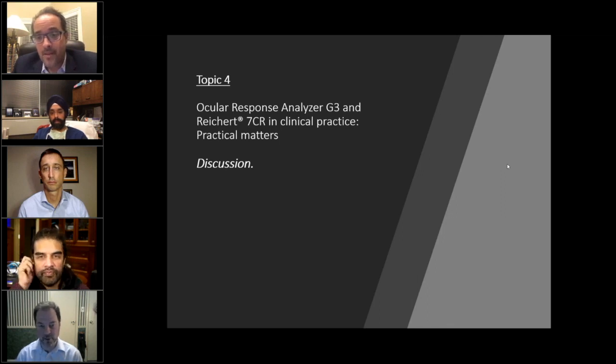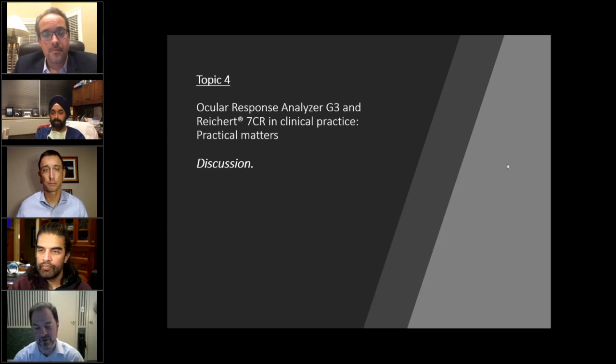That's right. Actually, that's when we really got a handle on what we were measuring: by looking at pre- and post-LASIK measurements and noticing how the two applanation events, what we call P1 and P2, changed in a different manner. The IOPCC algorithm was derived from pre- and post-LASIK data. We basically found a way to make the pressure stay the same in a pre- and post-LASIK population, and then did some other math and tricky stuff to also make it agree with Goldmann and everything else that makes it what it is today. But you're right, it was originally inspired by looking at changes after refractive surgery.